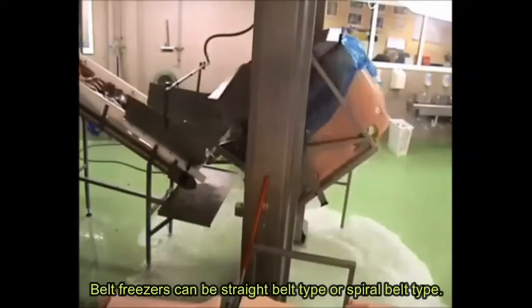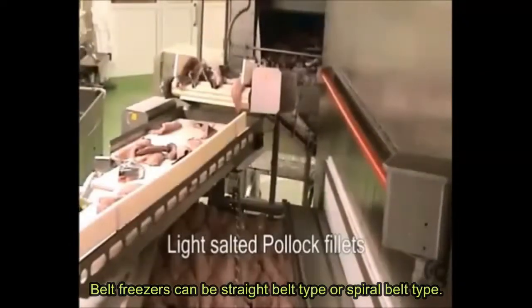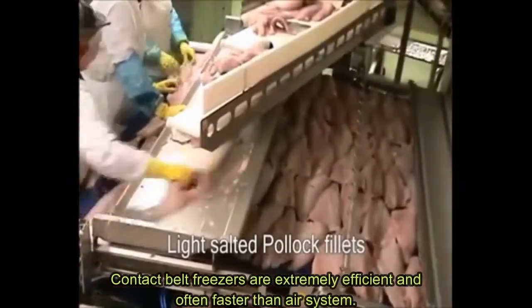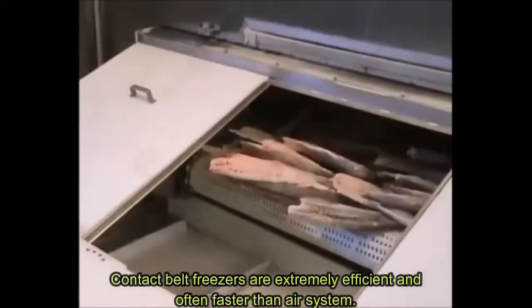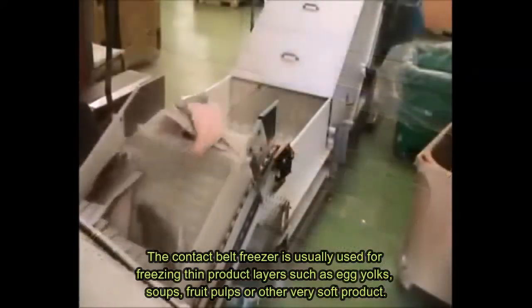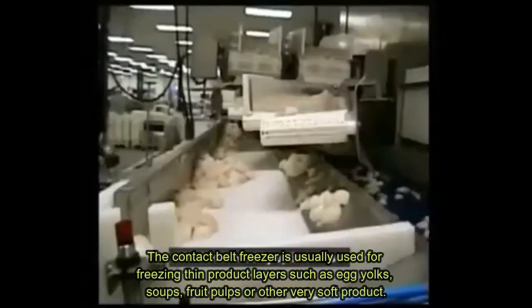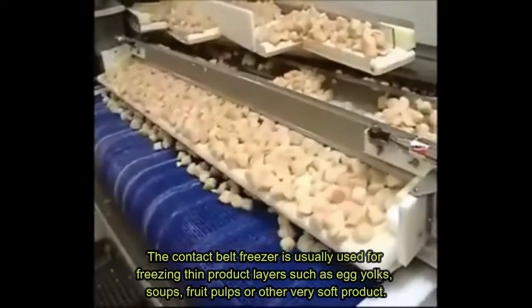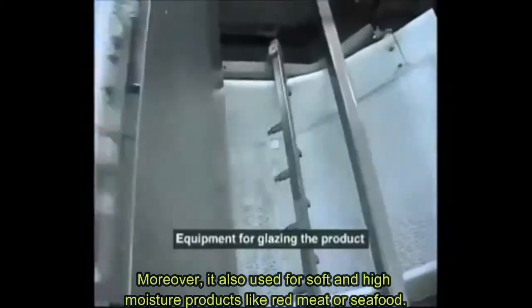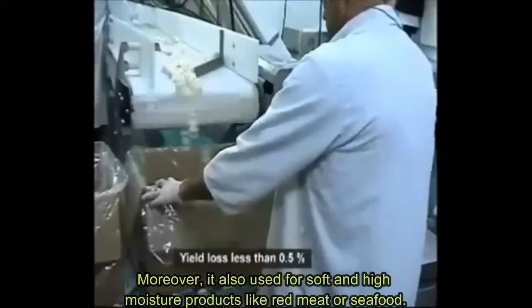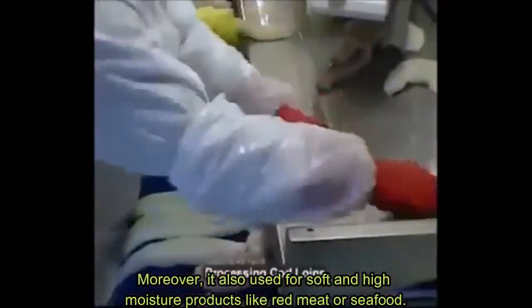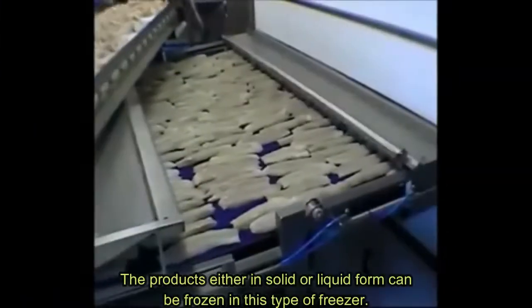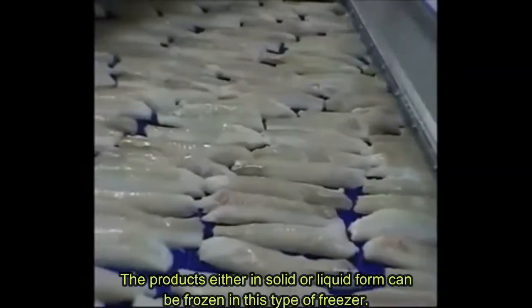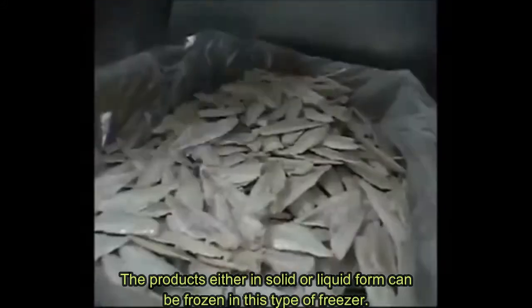Belt freezers can be of the straight belt type or spiral belt type. Contact belt freezers are extremely efficient and often faster than air systems. The contact belt freezer is usually used for freezing thin product layers such as egg yolk, soup, or other very soft products. Moreover, it is also used for soft and high moisture products like red meat or seafood. The product, either in solid or liquid form, can be frozen in this type of freezer.